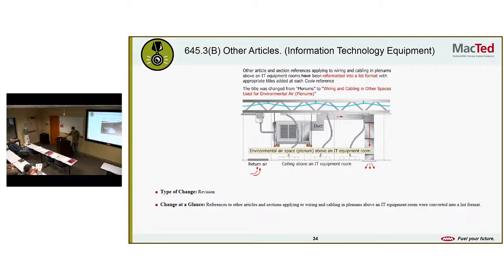Okay. We have a revision to Article 645.3, other articles. References to other articles and sections applying to wiring and cabling and plenums above an IT equipment room were converted into a list format, with appropriate titles added at each code reference. Well, there's a list format now that has to do with plenum space above IT equipment.